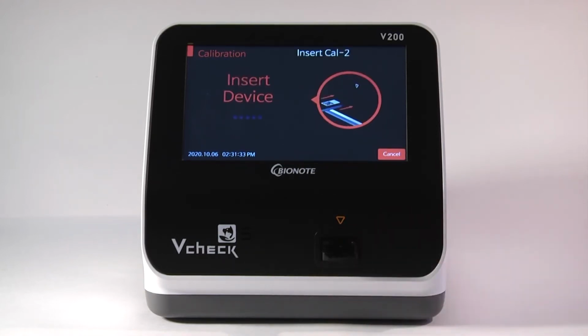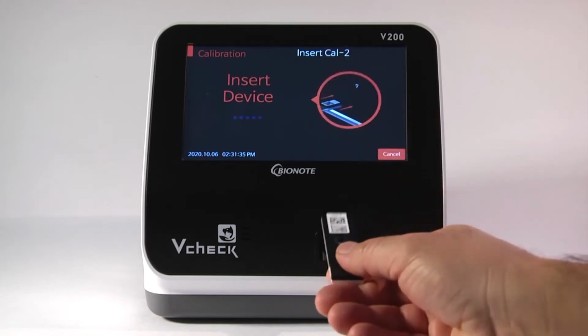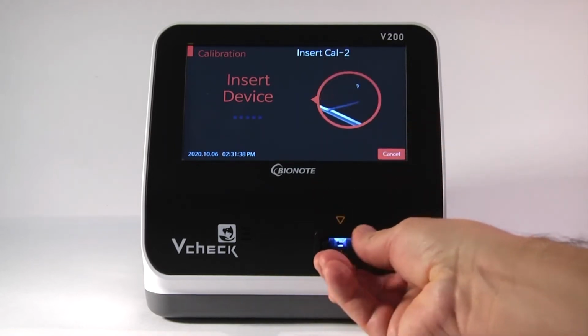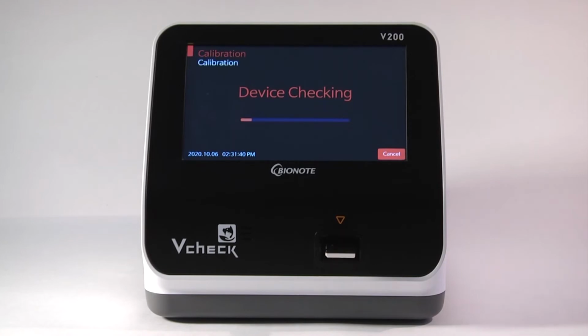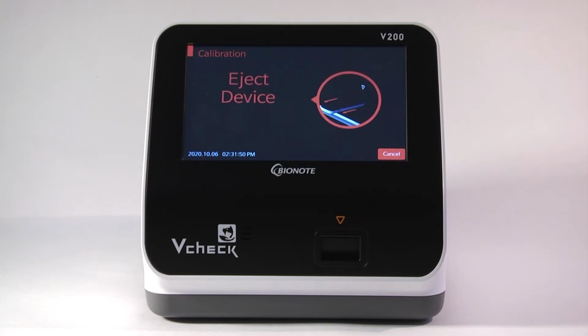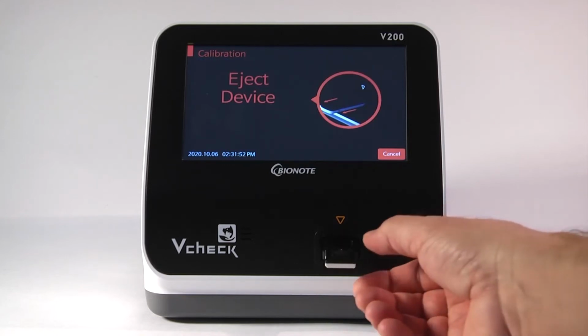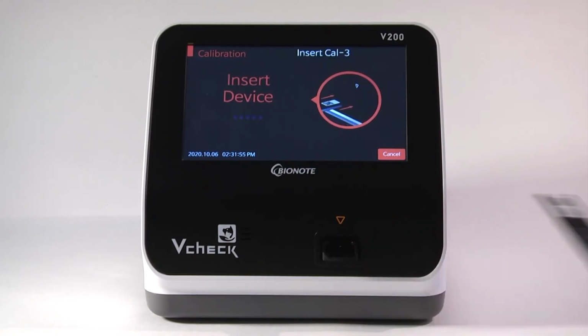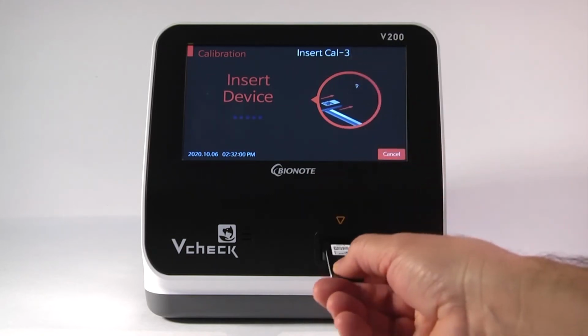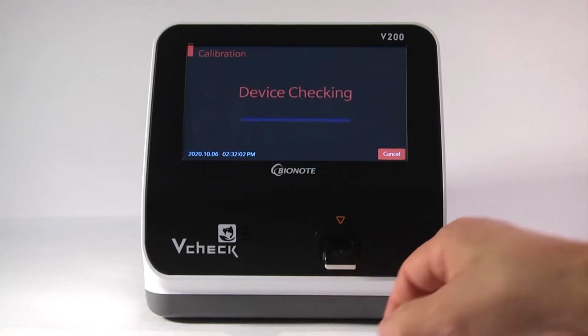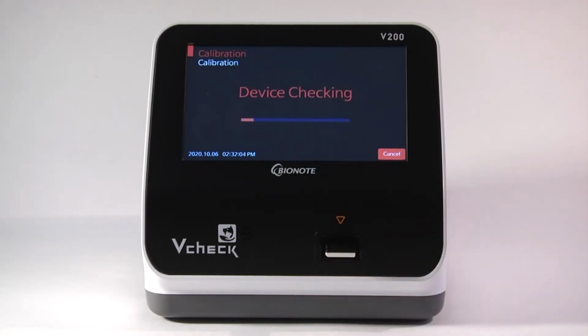Then insert Cal 2, which calibrates the ultraviolet sensor. When Cal 2 is complete, it will again eject for your removal. It will ask you to insert the next Cal. Insert Cal 3, again barcode up into the cradle until it clicks. The Cal 3 is going to calibrate the red, green, and blue sensor on the analyzer.